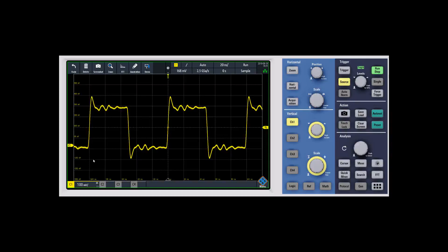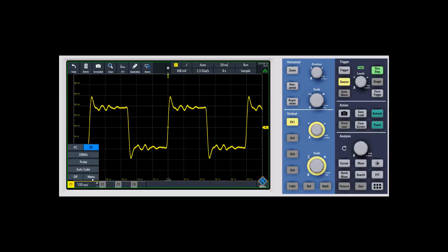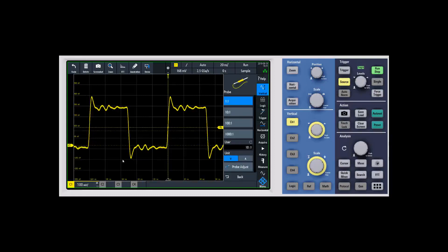The simplest way to do this is, for the different channels that you have turned on, when you click on the channel itself, there is an option to go into the probe setup.